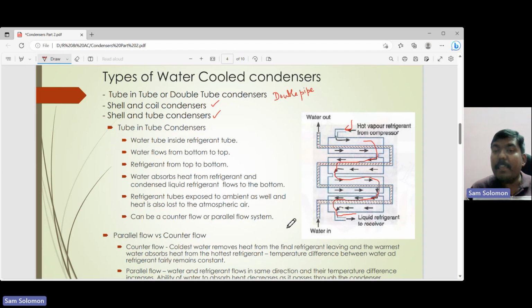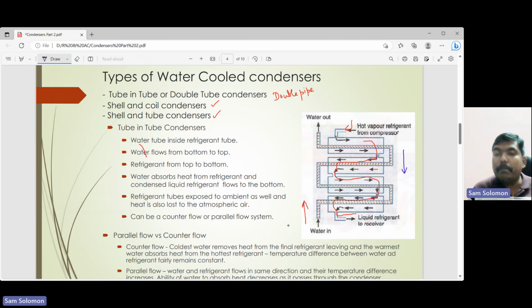The other point is that it can be either a parallel flow system or a counter flow system. What is shown here is a counter flow system. You can see water moving from bottom to top. And let me use another color over here. So let me use blue. So you have the refrigerant moving from top to bottom. The entry of the refrigerant is at the top, the entry of water is at the bottom. So the flow is opposite to each other, so we call it counter flow.